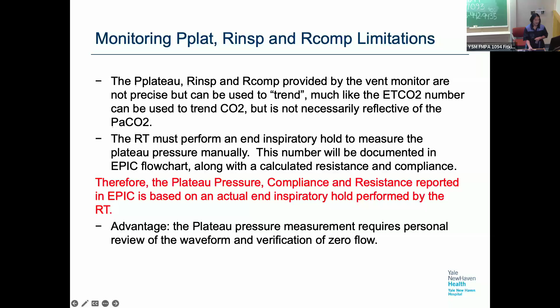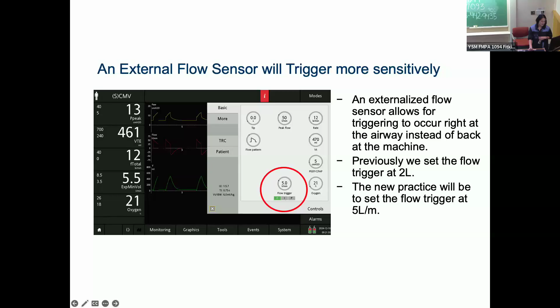I think it's good. The external flow sensor, if anyone's paying attention, will trigger more sensitively. And so the company has recommended to us that the flow trigger, really the starting setting, should be 5 liters per minute. For those of you that have been paying attention to this on the Avias, we usually start around 2 or 3. Don't go down on it. This is due to the location of the sensor. Okay.